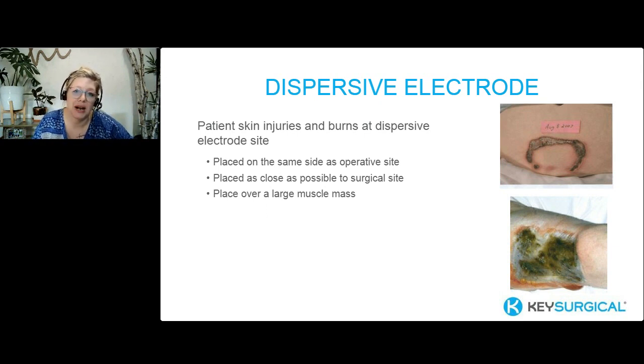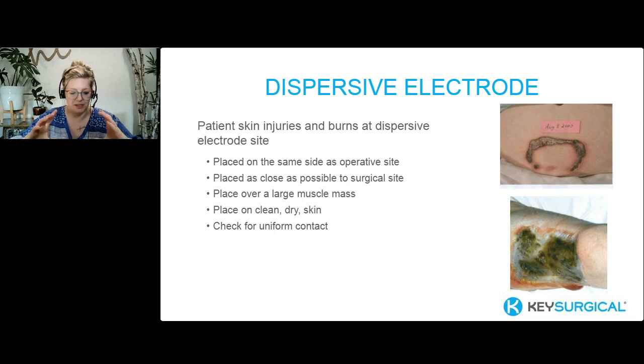Place it on clean, dry skin. Check for uniform contact, with no edges peeling off. It's very stable on the patient's skin. Never ever cut, alter, or fold a dispersive electrode.